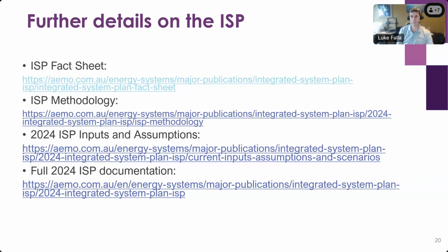We build the actual option within our cost database and have a fairly robust estimate. So we don't do it on a per voltage or per kilometer basis or anything like that. It is for the renewable energy zone where we have the linear expansion, and it's based on how many megawatts per $1 million. That's the type of metric we have for those ones. But we build each actual transmission upgrade option into our full transmission cost estimate.